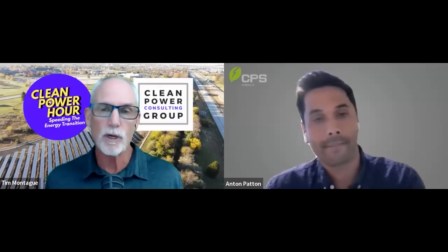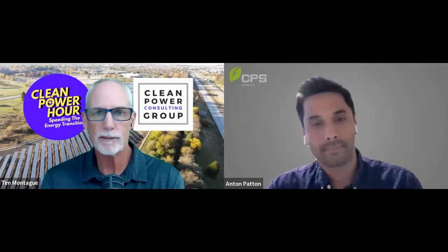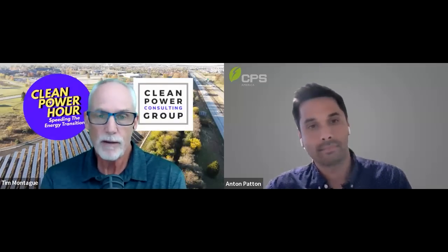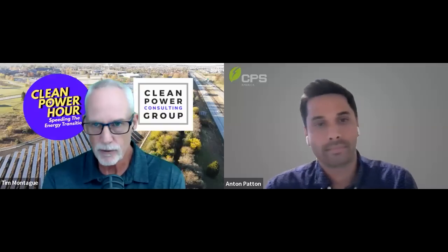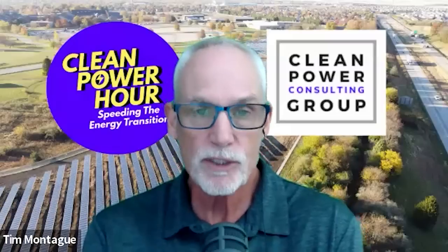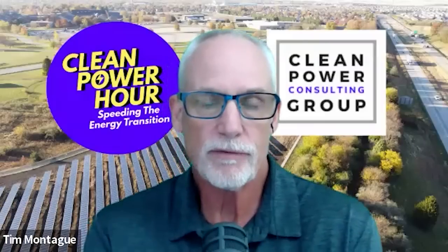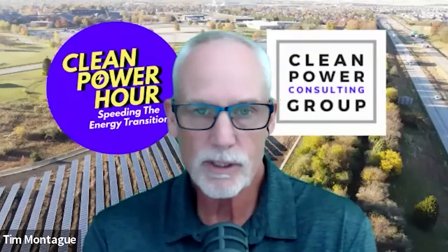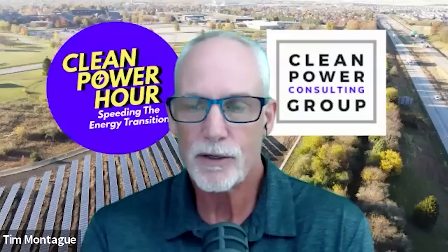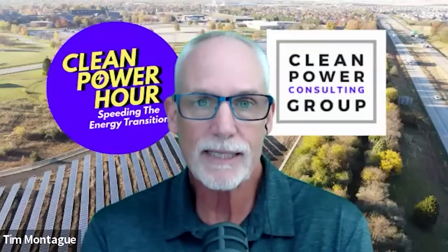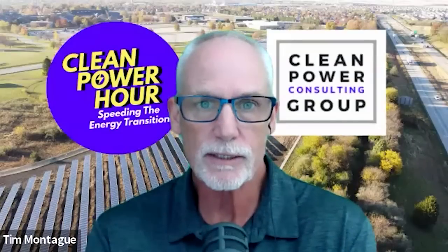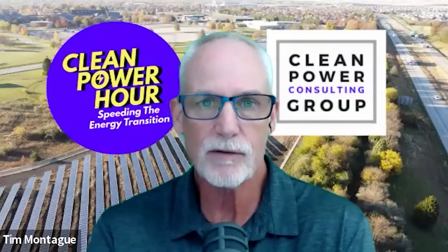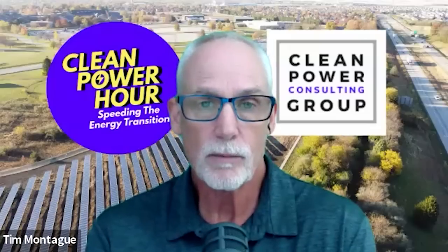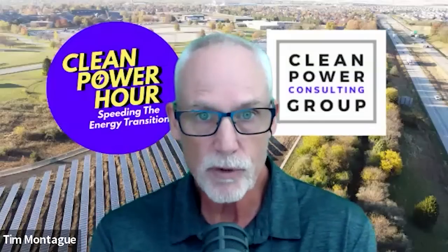So when you think about a 100 megawatt power plant done traditionally with 5 megawatt inverters, you have at face value 20 inverters. Switching over to string inverters, if I did the math on a 275 kW inverter, you're almost 20xing the number of inverters in the project. You've got over 360 inverters in a 100 megawatt plant if you're using string inverters.